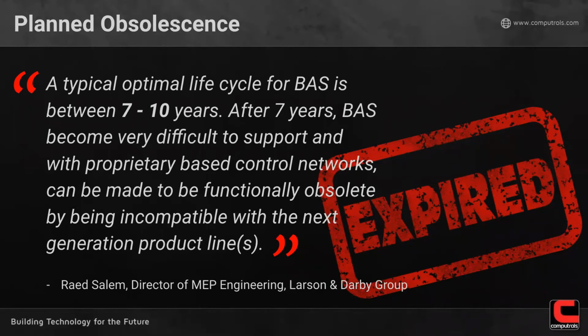You'll say, okay, I'll replace this controller then. And they may also tell you this new controller won't work with your version of software, so you're going to need to upgrade that as well. Unfortunately, a lot of service partners aren't really aware of the life cycle of those individual controllers and products, so it's difficult for them to tell you where you are in that life cycle. But it's something you need to be acutely aware of, because it could mean an extremely large expenditure at some point that's out of your hands, with the manufacturer telling your service partner this is no longer supported.